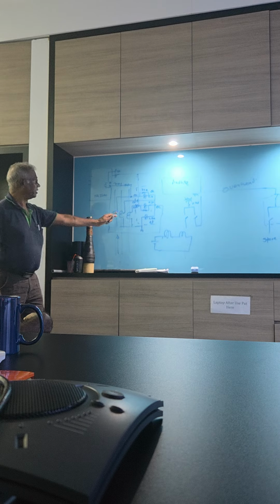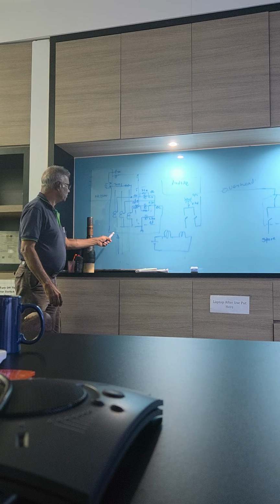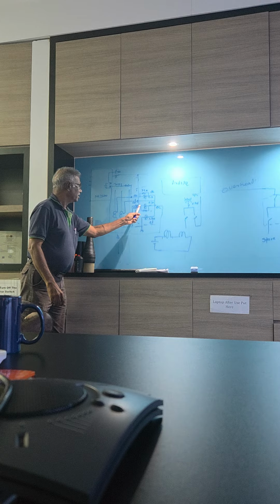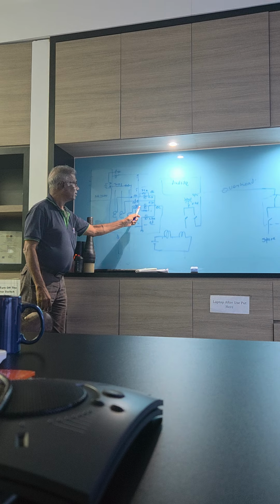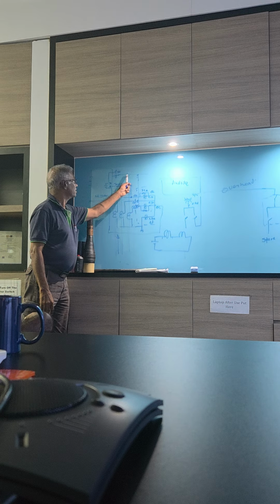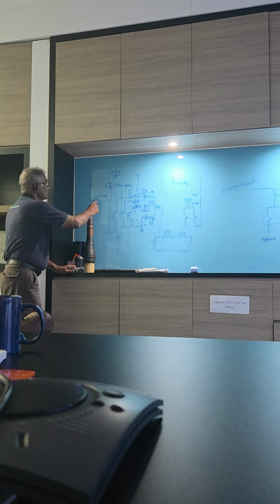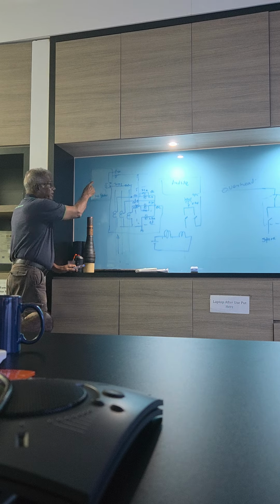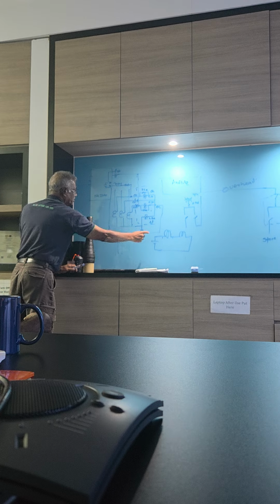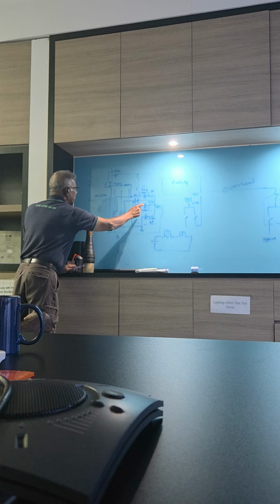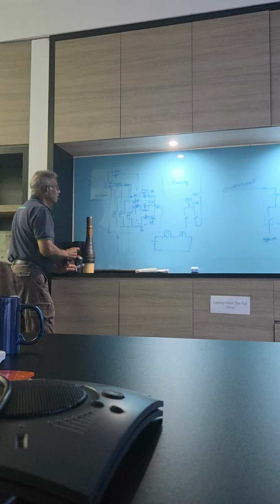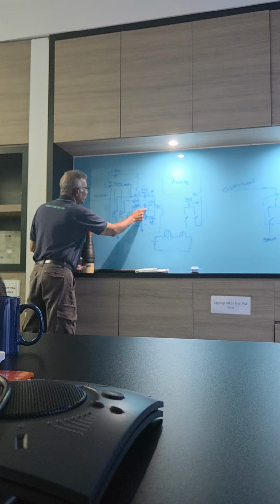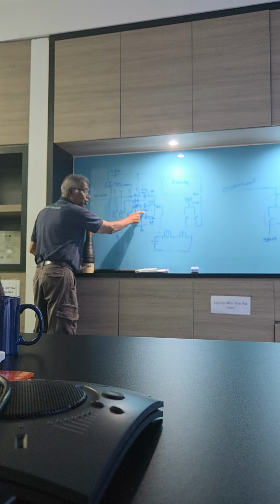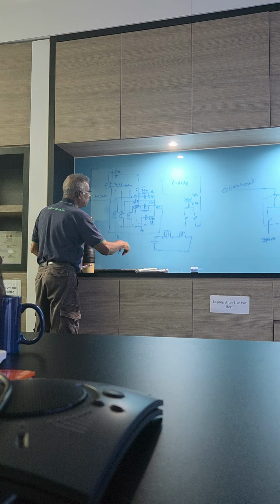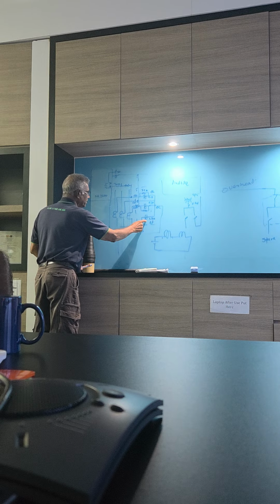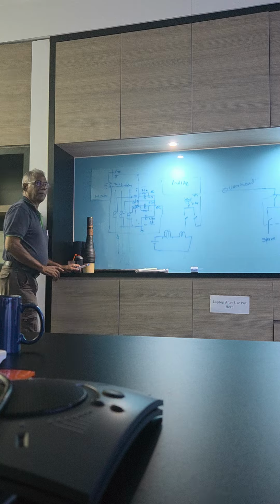Yeah, it trips. After that it trips because you have a positive here, it straight goes to this end. They cut here and this coil, they put the negative here. So when they simulate this relay, the positive goes here, and opens this, calls this relay. But at that time, that's why we don't know, it cannot be like this because this fuse will blow off. So very possible it's not this relay lah. They would have called this and it tripped.